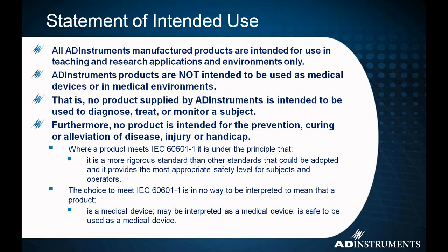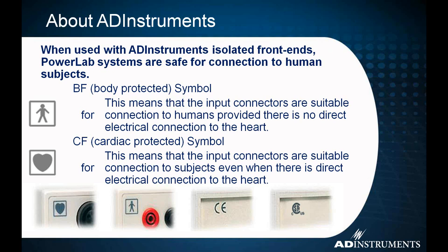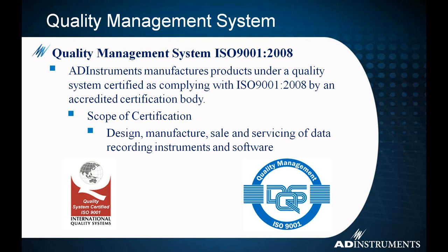These next couple of slides have been added because customers ask these questions frequently. The basic take-home message: ADInstruments products are not intended to be used as medical devices or in medical environments. Do not use our equipment to diagnose, treat, or monitor a subject. They can be used in the clinical environment for research, but not for actual diagnosis or treatment. We use international safety symbols for body protection or cardiac protection. If there is direct electrical connection to the heart, we have the heart symbol; if approved for connection to humans with no direct electrical connection, we have the body-safe symbol. We also comply with EU, US, and Canadian safety standards for medical devices.